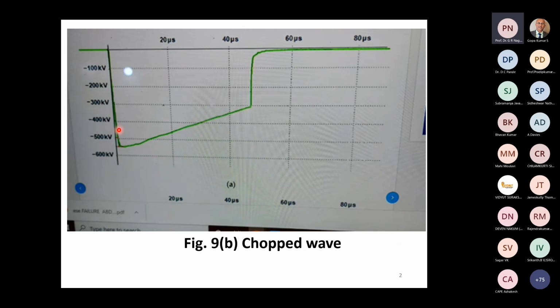Suppose I increase this voltage to a higher value - you will find it breaks down much earlier. So higher voltage means shorter time to chop. Starting from a very low probability, as I go to a higher voltage, there is a very high probability of flashover. We plot a curve of the peak voltage before flashover against the time to chop, and call that the voltage-time-to-flashover characteristic.